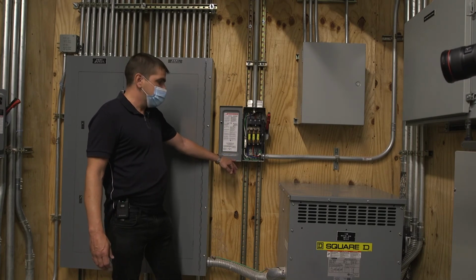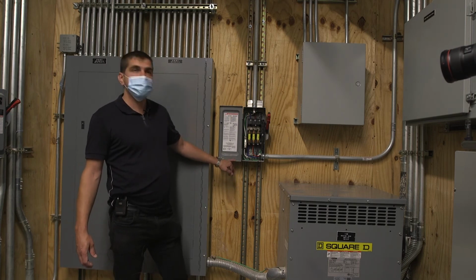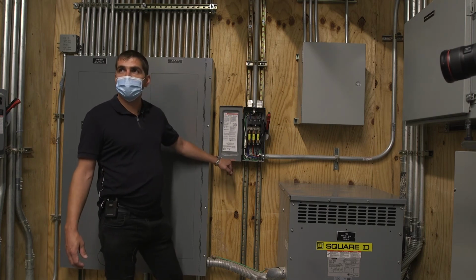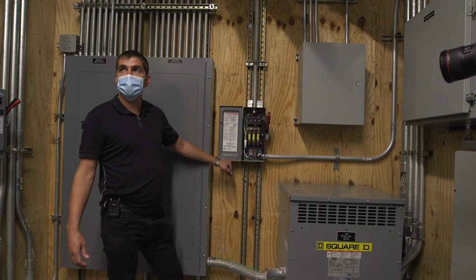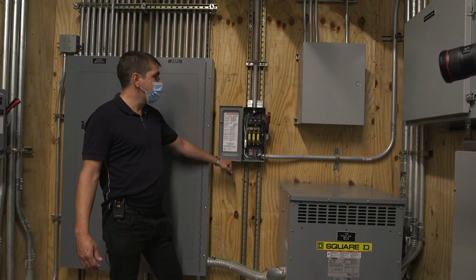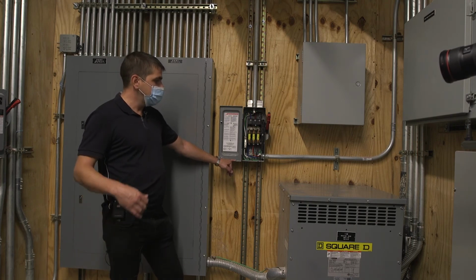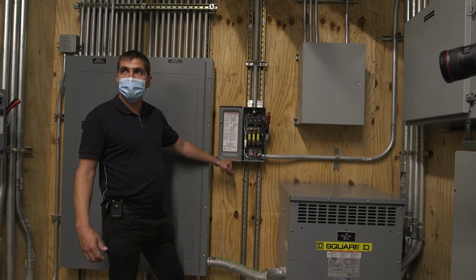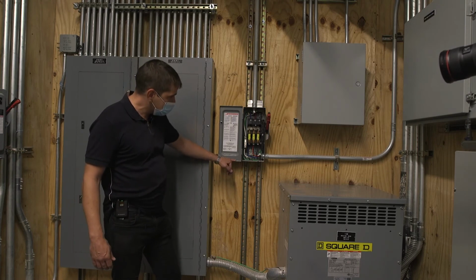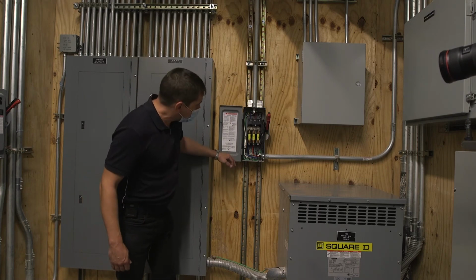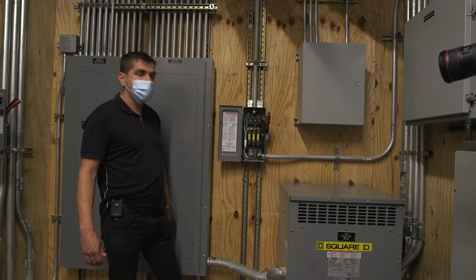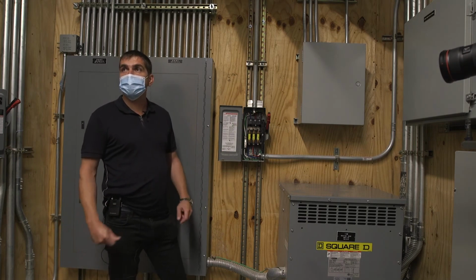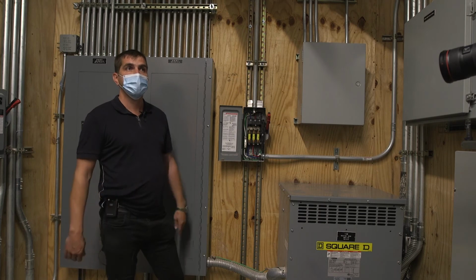Once in a while, probably once a year, it's recommended for the fuse disconnect switches to be checked for their operation, that they can be turned off and turned on. So once a year, the good idea is to come to the disconnect switch, put it in the off position, and make sure that all of the contacts are disconnected, so it operates properly. Other than that, no specific maintenance required.